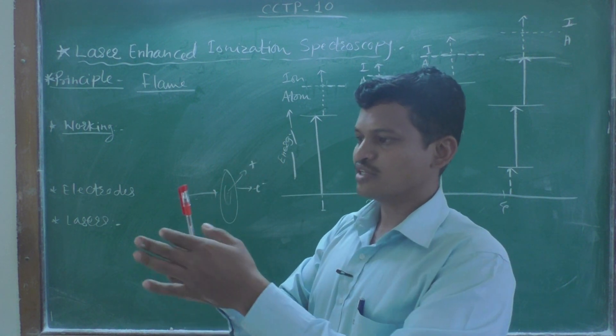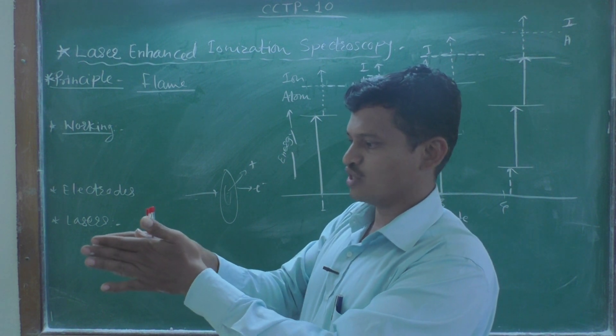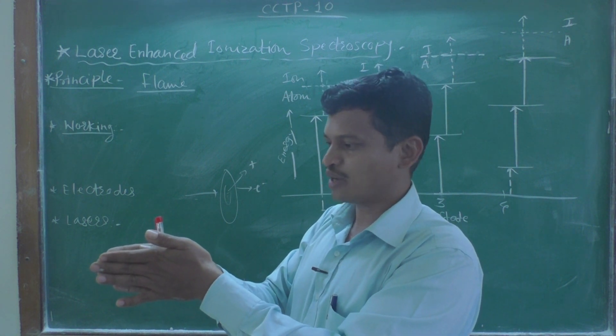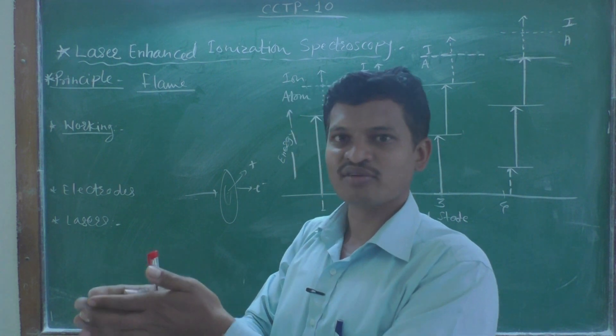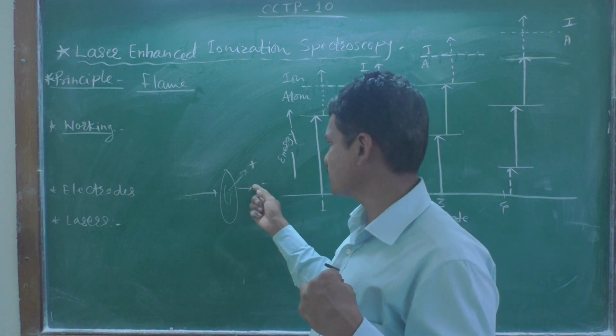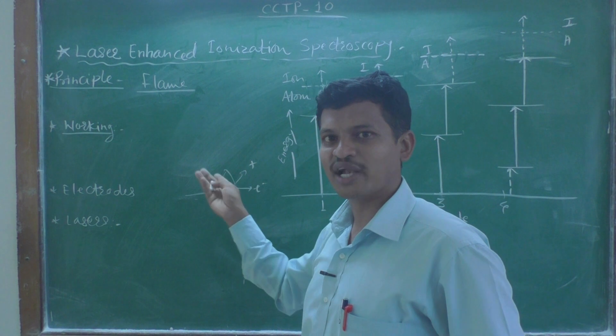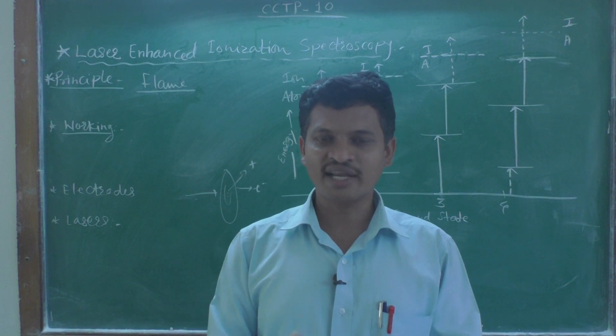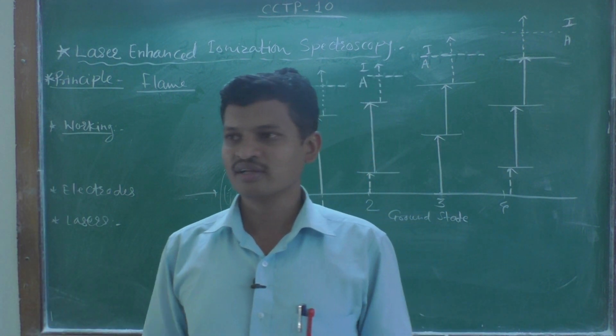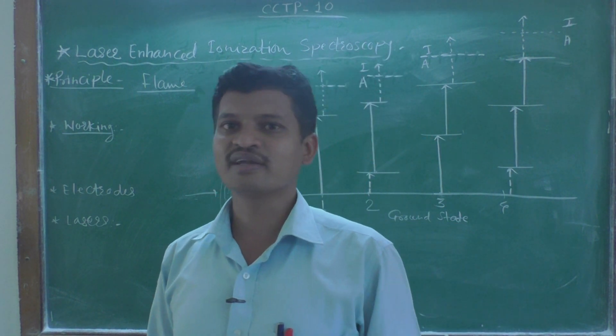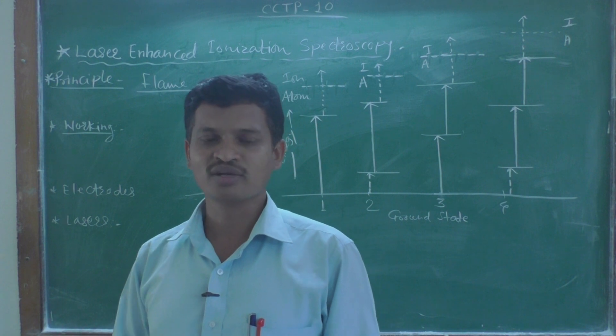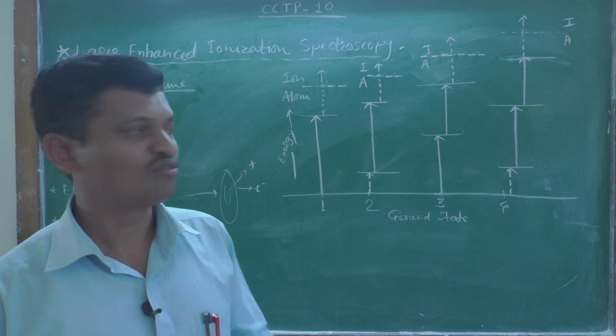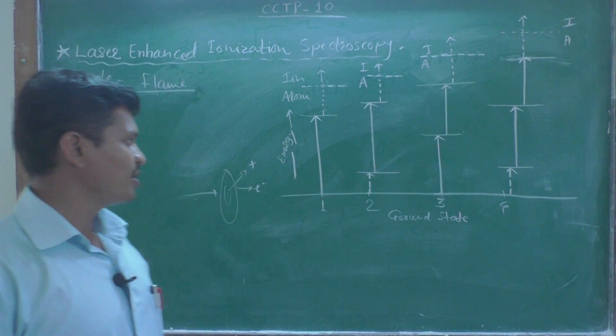If this red color represents the flame, the electrodes are positioned parallel to each other on either side of the flame. As soon as ionization takes place, the positively charged ions are attracted towards the cathode and electrons towards the anode. The further process is then handled by the detector, amplifier, and readout devices — the optical and electronic system.